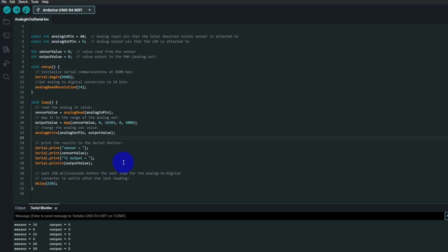Now this is not a temperature compensated reading, so this is based on you taking a measurement at 25 degrees C. The conductivity of the water rises as the temperature of the water rises, which is why the commercial instrument has got a temperature sensing bulb, and it compensates the reading based on the temperature measurement of the liquid being measured.